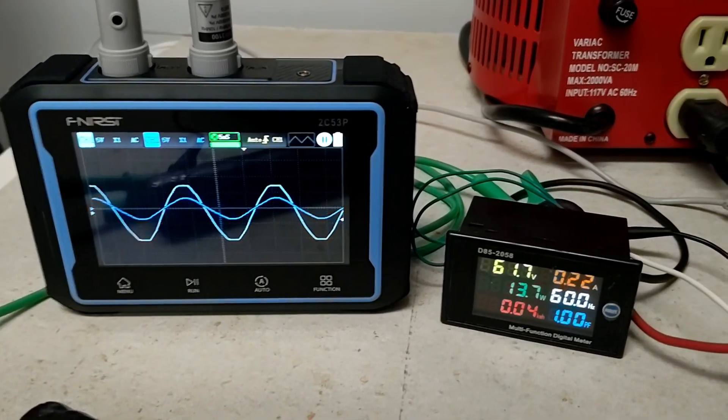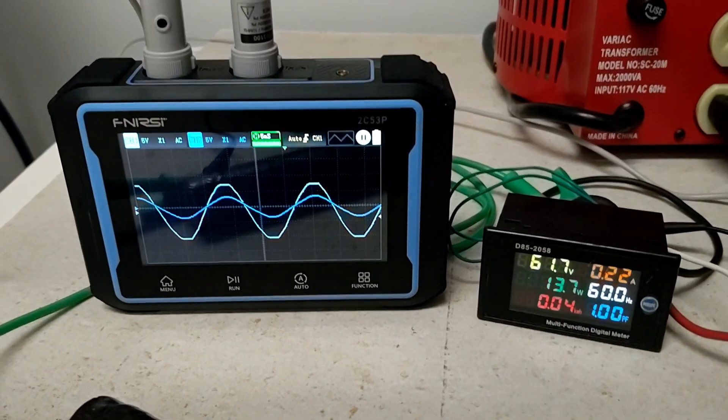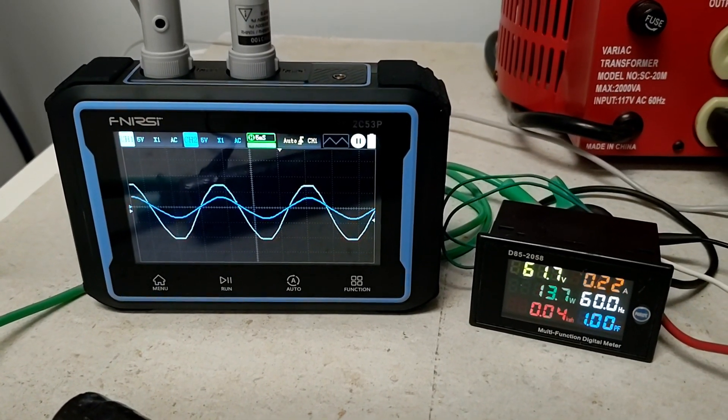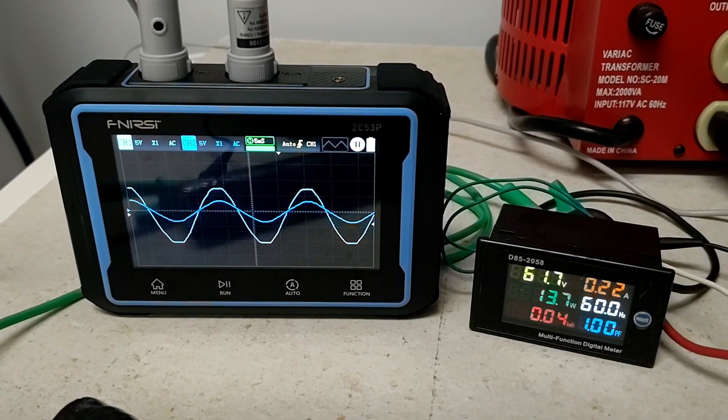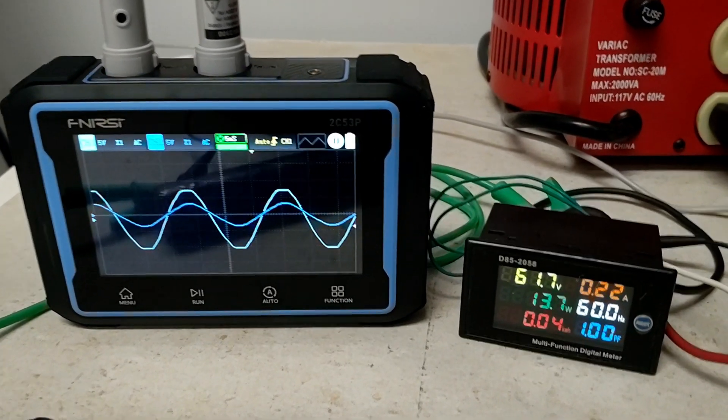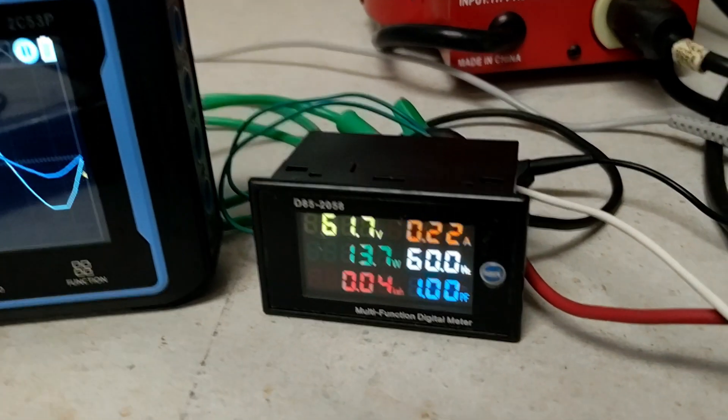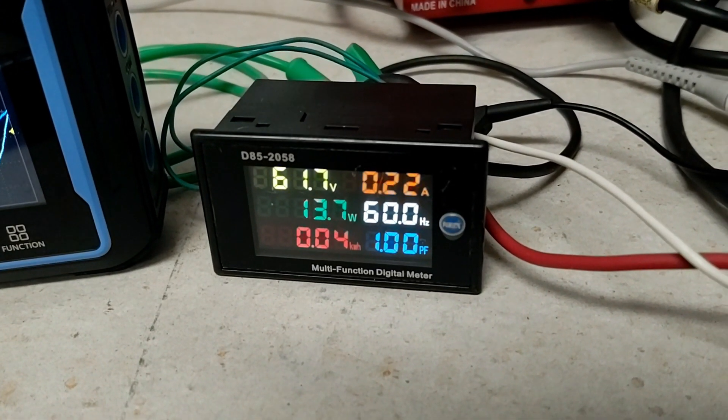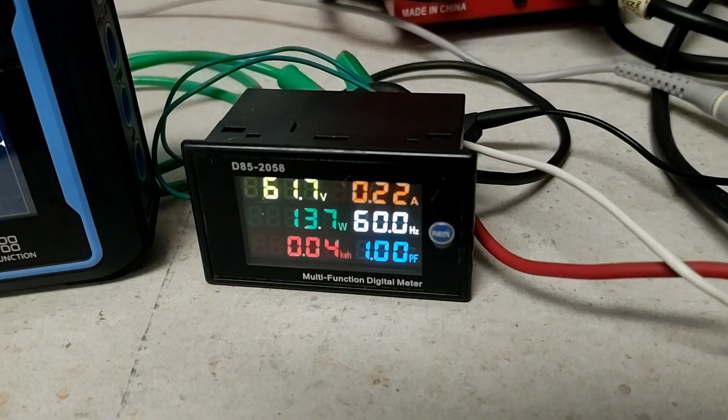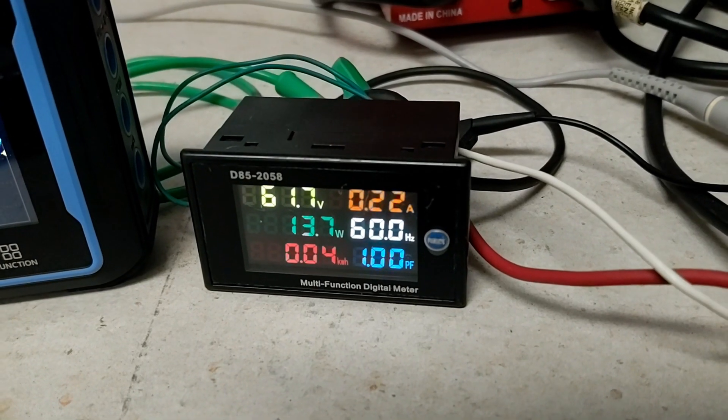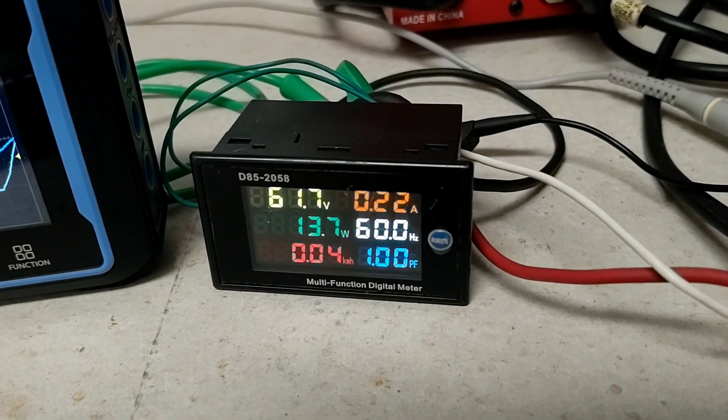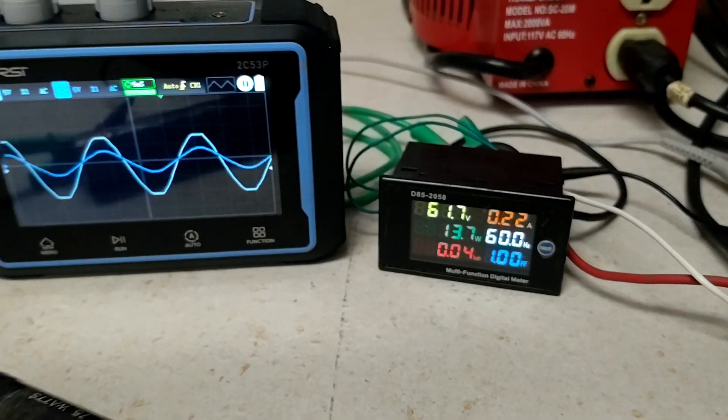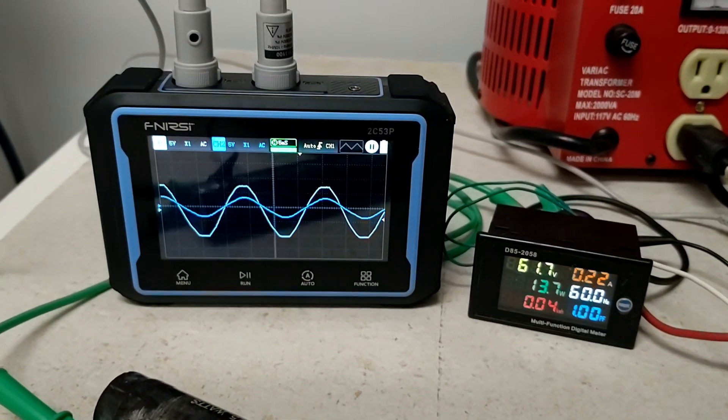Notice that now our current is in phase with our voltage, and the power factor has gone back to 1. You can also hear the motor's running a little better.